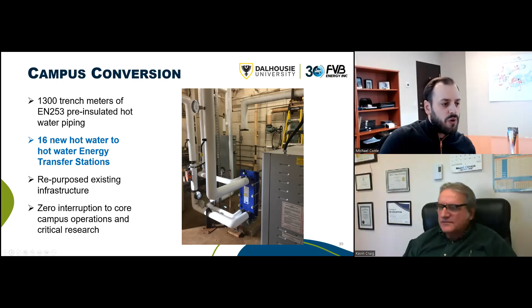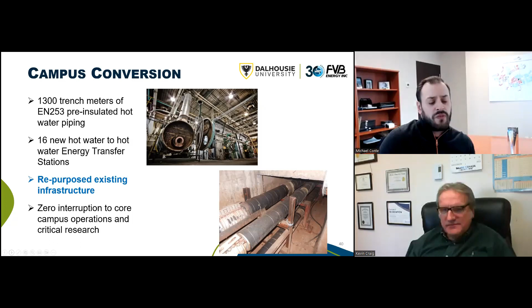In addition to the boiler we were able to repurpose, we also utilized some dual steam lines that had been installed. Lucky for us, when the engineer put this piping and these tunnels in the ground in 1968, they decided to go with fully redundant steam and condensate lines for a portion of the system. Working with the contractor, we did a full inspection of these tunnels and found the two steam pipes were actually in fairly decent shape. We designed out the replacement of some compensators and upgraded some of the steel supports, but we were able to reuse a good portion of these steam lines, which is one of the main arteries connecting the north and south campuses. This really helped control project costs and utilize an existing asset that otherwise would have just been a sunk cost.